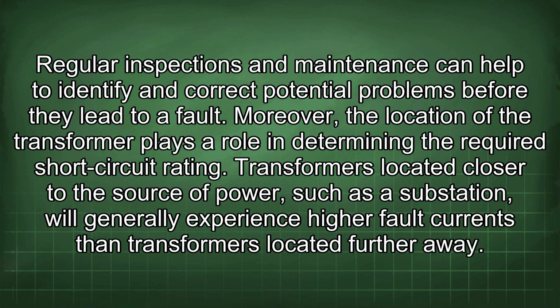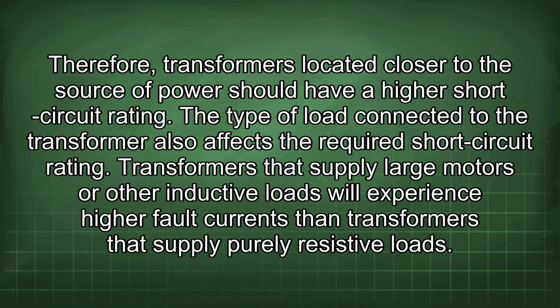Moreover, the location of the transformer plays a role in determining the required short-circuit rating. Transformers located closer to the source of power, such as a substation, will generally experience higher fault currents than transformers located further away. Therefore, transformers located closer to the source of power should have a higher short-circuit rating.